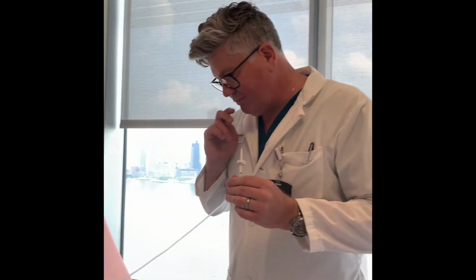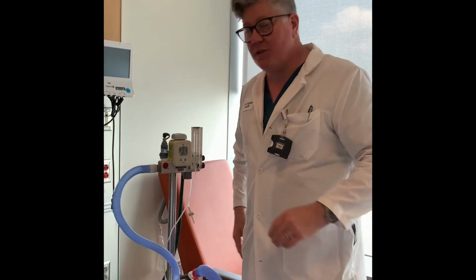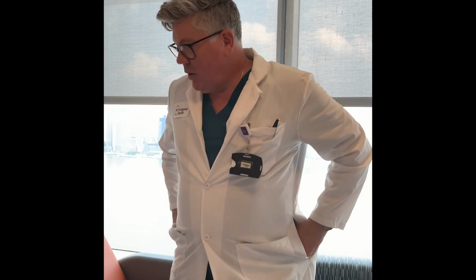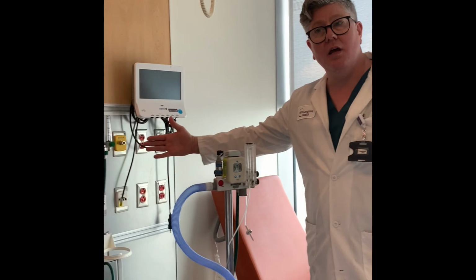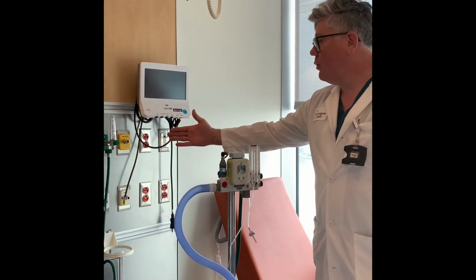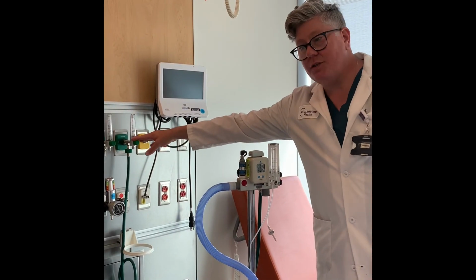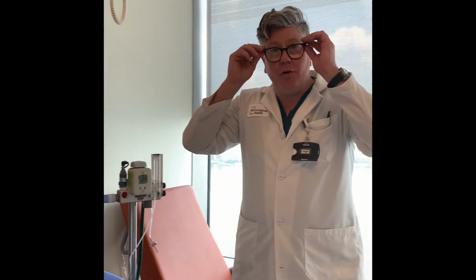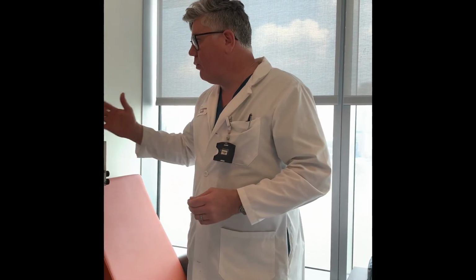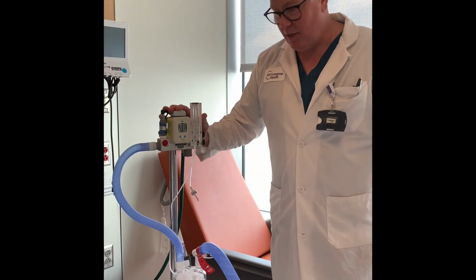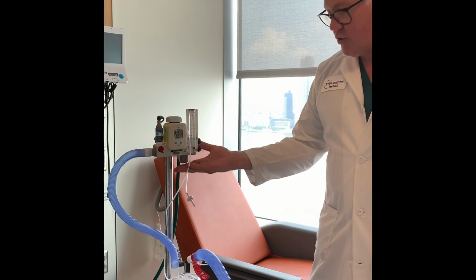And why would you use this machine versus a Vapotherm? Well, they do the same thing. One of the advantages of this machine is that it just runs off of oxygen. So in a room like this, where you have air and oxygen available, you could use a Vapotherm, correct? And they do basically the same thing. But in a room where there's no medical air available, this is the best option because you don't need medical air because it entrains it itself.